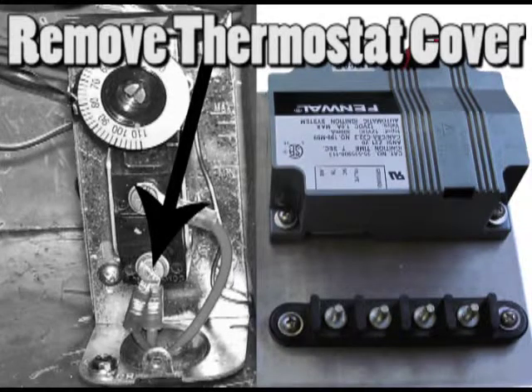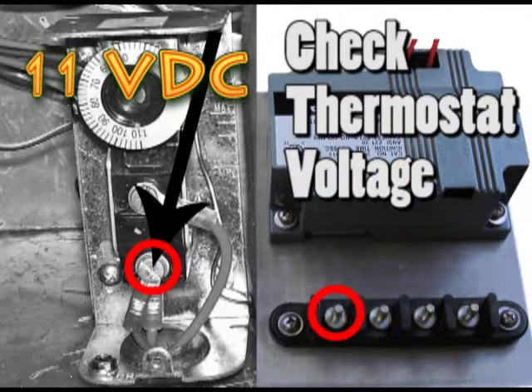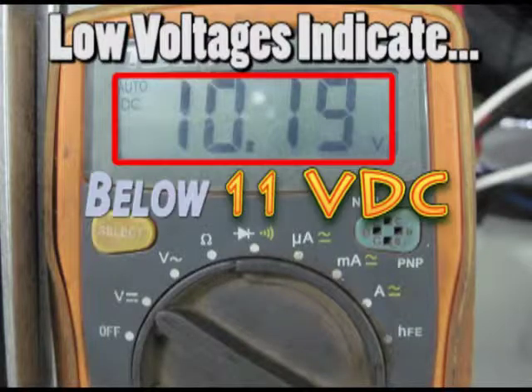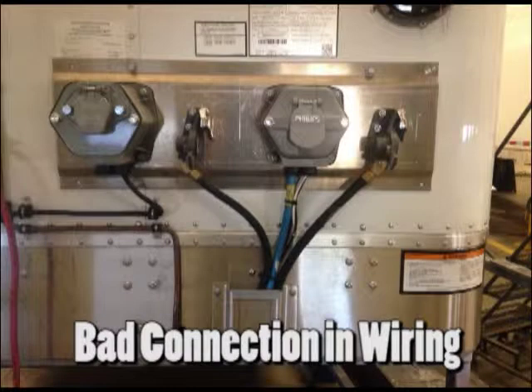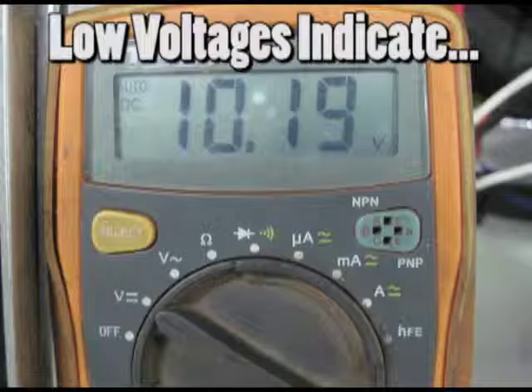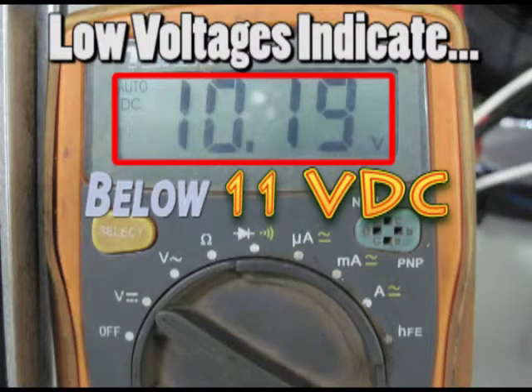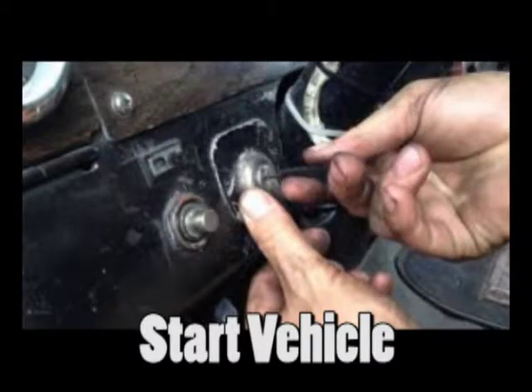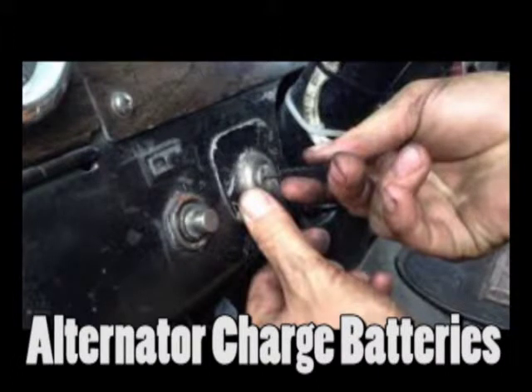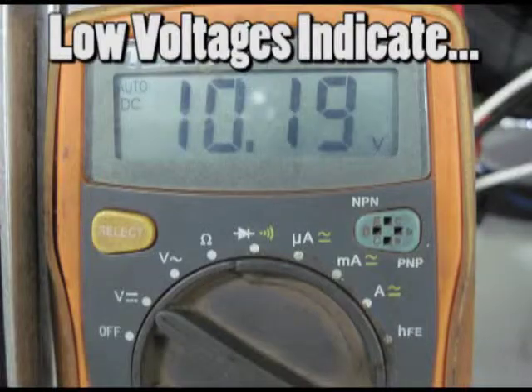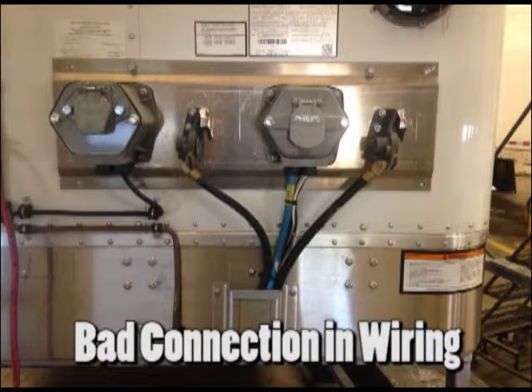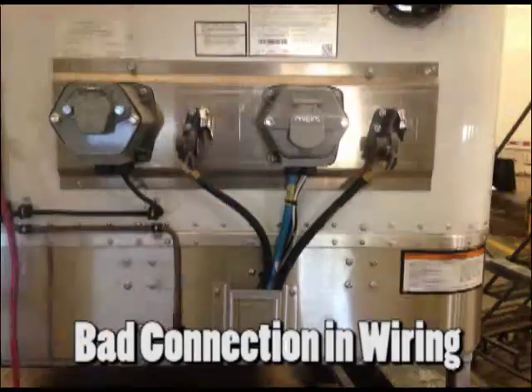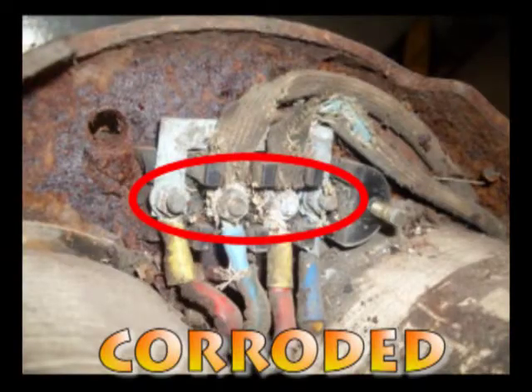Remove the cover to the thermostat and check that the heater is receiving at least 11 volts DC while the blower is running. A voltage below 11 volts DC typically indicates a low battery or a problem in the electrical system between the heater and the vehicle. If the voltage is below 11 volts DC, start the vehicle and let the vehicle's alternator recharge the battery for 15 minutes before attempting to start the heater again. If the voltage is still low with the vehicle running, there is a problem in the electrical system between the heater and the vehicle. Start by looking for loose or corroded connections.